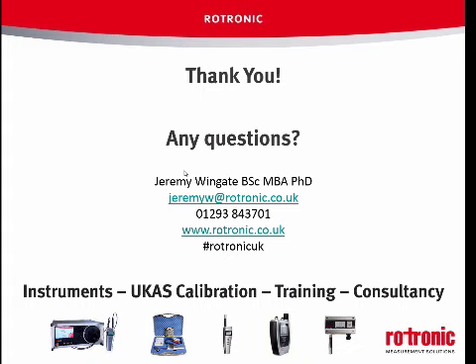We state 0.8% on our sensors in terms of accuracy, and if they're left next to each other in maybe a little box so that they're vaguely stable for temperature and there's no air passing over them, you'd expect them to be within 1.5%, 1%, if not better. But we get people ringing up saying a sensor reads 2% out, it's broken. Well, put them back in the lab, put them next to each other, and they're absolutely identical. So it's a difficult one. There's no right answer, I'm afraid.